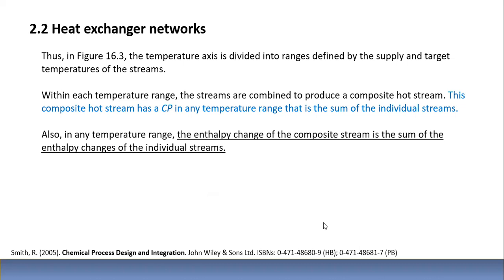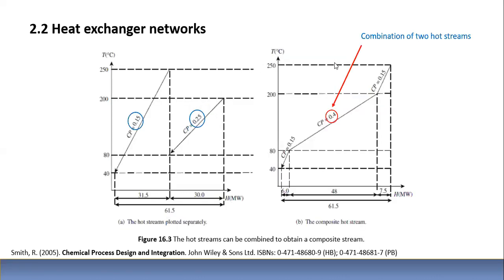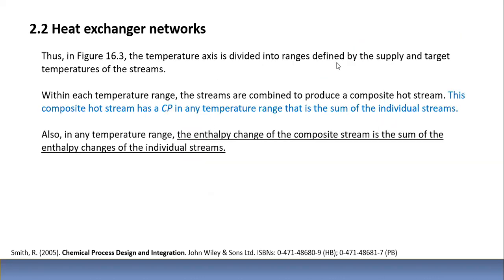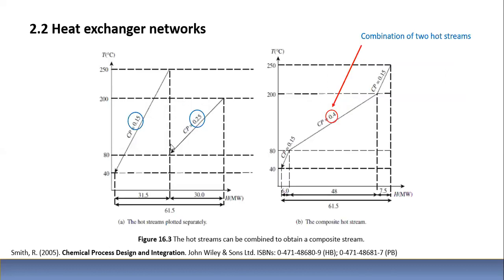In figure 16.3, the temperature axis is divided into ranges defined by the supply and target temperatures of the streams. Within each temperature range, the streams are combined to produce a composite hot stream. This composite hot stream has a CP in any temperature range that is the sum of the individual streams, as long as they overlap. In this region of temperature where they overlap, you can add them up and then you have a new slope as a result of the addition of the two CPs.